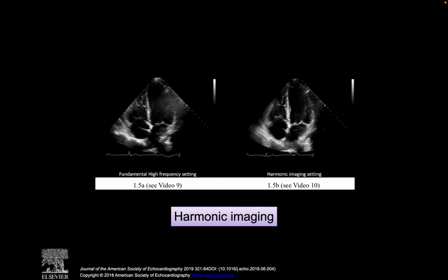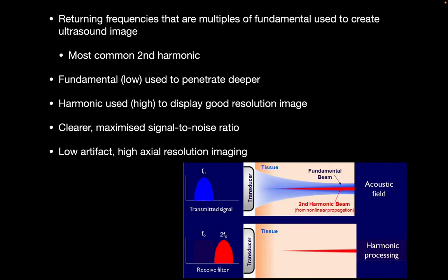Harmonic imaging. Usually harmonic imaging is used in most modern ultrasound machines. The physics behind it is quite complex, but most modern systems, they emit in your base frequency, so that's your transmit frequency. The sound waves will penetrate the tissues and they will generate the echoes, but not only from that base frequency, they're gonna be producing echoes in the multiples of that base frequency as well at the same time. And the higher the frequency with the receiving signal, the better the image quality.